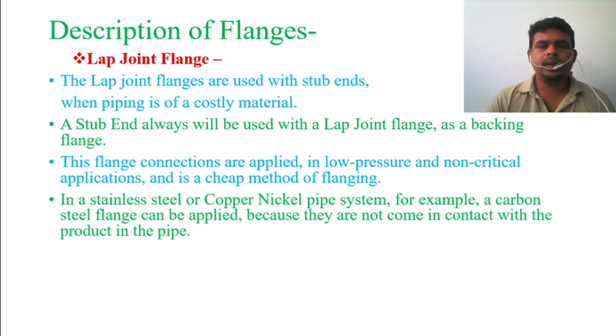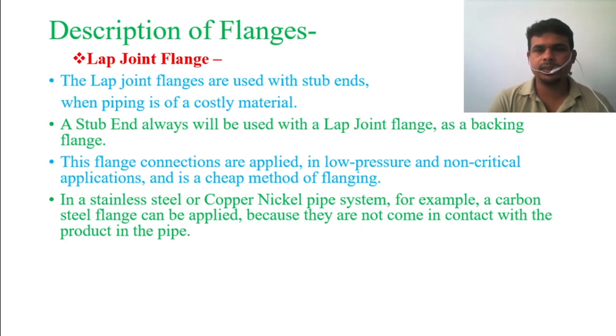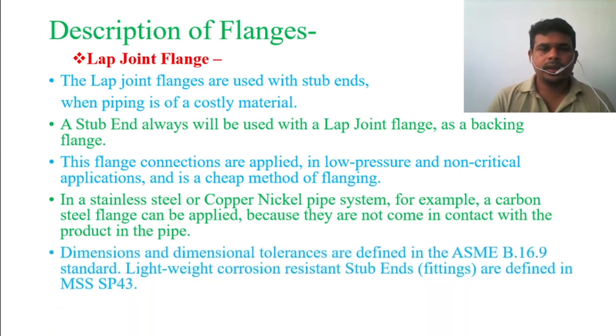For example, in a stainless steel or copper-nickel pipe system, a carbon steel flange can be applied. If your main pipe is stainless steel or copper-nickel, you can use the cheaper carbon steel flanges with the lap joint type, because the flanges do not come in contact with the product inside the pipe. The dimensions and dimensional tolerances for this type of flange are defined in ASME B16.9 standard, and lightweight corrosion-resistant stub end fittings are defined in MSS SP-43.